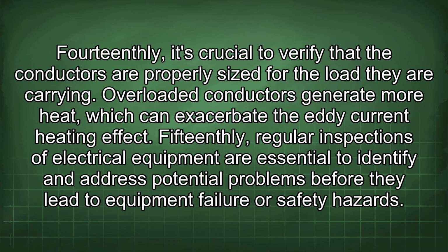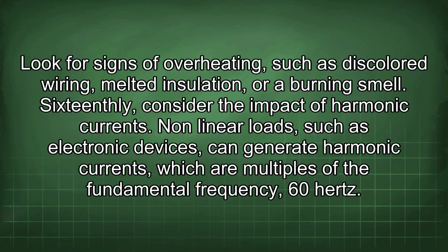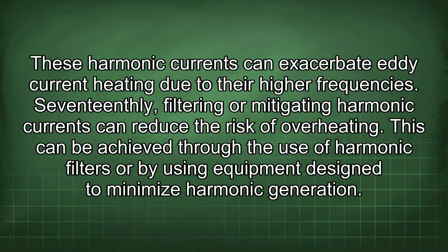Fifteenthly, regular inspections of electrical equipment are essential to identify and address potential problems before they lead to equipment failure or safety hazards. Look for signs of overheating, such as discolored wiring, melted insulation, or a burning smell. Sixteenthly, consider the impact of harmonic currents. Non-linear loads, such as electronic devices, can generate harmonic currents, which are multiples of the fundamental frequency, 60 Hz. These harmonic currents can exacerbate eddy current heating due to their higher frequencies. Seventeenthly, filtering or mitigating harmonic currents can reduce the risk of overheating. This can be achieved through the use of harmonic filters or by using equipment designed to minimize harmonic generation.